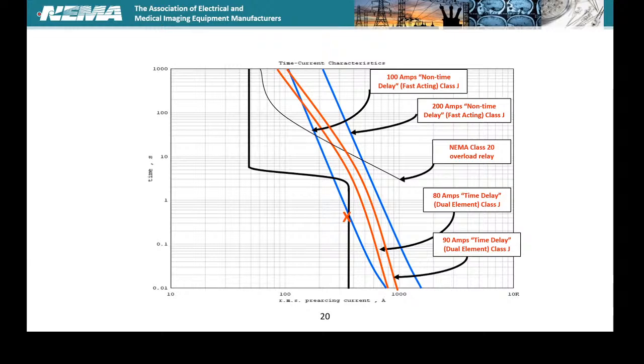I would say that the big exception to that is for a variable frequency drive, where you do want to use a very fast acting fuse to protect the drive, even though it's feeding a motor. Right, and the difference there is when you put a fast acting fuse on a variable frequency drive, it will not see the inrush current. That's the beauty of a variable frequency drive. It controls that motor during its start time. So you would put that fast acting fuse on the supply side for that variable frequency drive, and that would be a prime example of a non-rotating load, because the VFD does not give you inrush current. Although it's serving a rotating load, it takes care of ramping that motor up to speed.